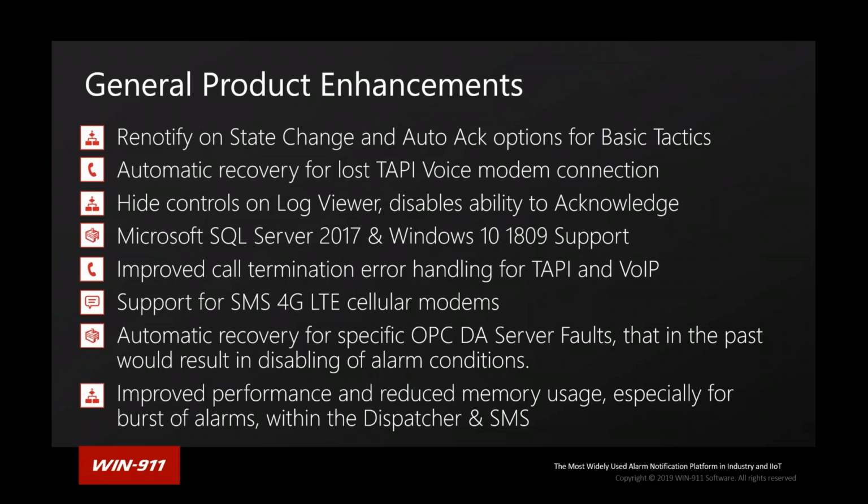We will wait for another update to come through that becomes a good quality at some point, and we continue on monitoring this item. So the three server faults that we are checking for to maintain a connection with would be a server shutdown, RPC server unavailable, and an unspecified error. It actually comes through listed unspecified error. We feel those three are recoverable faults, so we continue to hold the handle for those items.